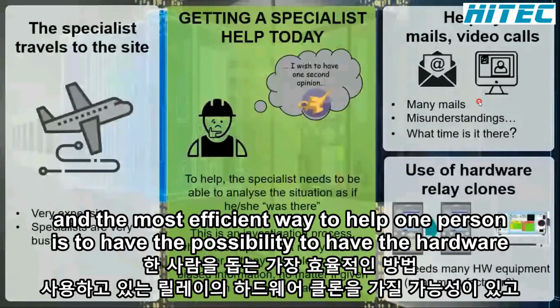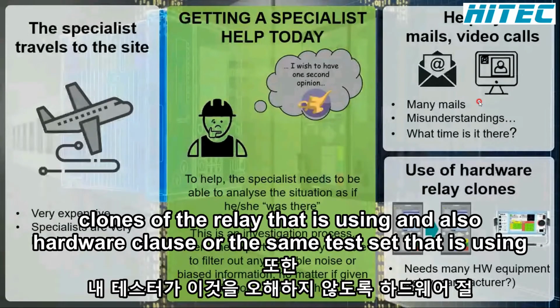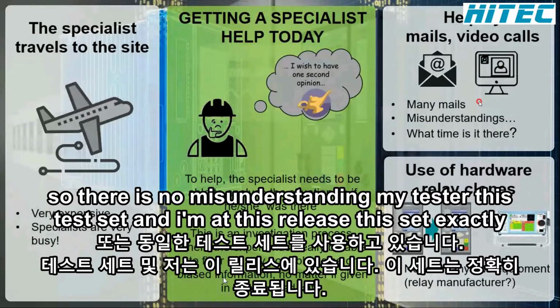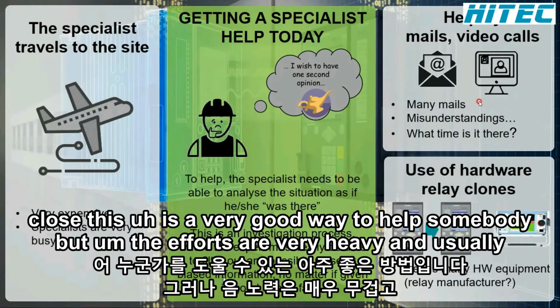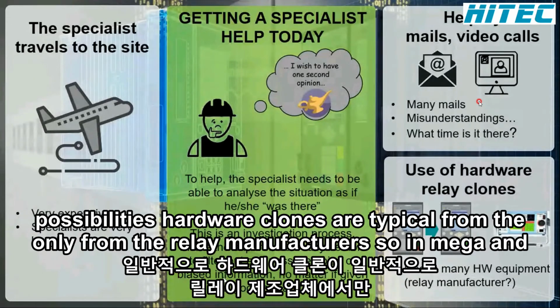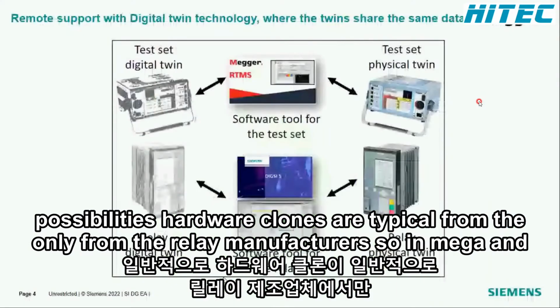The most efficient way to help someone is to have hardware clones of the relay he is using, and hardware clones of the same test set, so there's no misunderstanding: my test set matches his test set, my relay matches his relay, except they're clones. This is a very good way to help, but it's very costly, and usually only relay manufacturers can provide hardware clones.